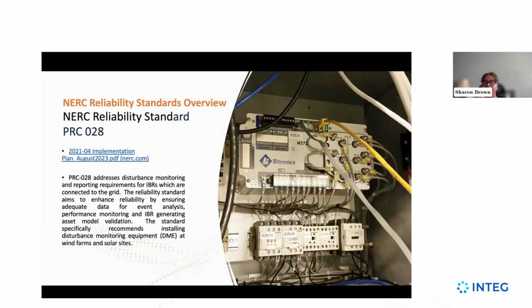You can't carry it like synchronous generation, like a big frame unit with all that metal spinning, the inertia. You can't ride through a fault like a gas turbine carries frequency. But because of the amount of penetration in certain markets, particularly like ERCOT, it's literally no longer an option for folks to just drop off and say, okay, we had a fault, we're disconnecting from the grid. That's the way it used to be, right? Well, here, that dog don't hunt anymore, as my grandmother used to say. And FERC has seen, with the various disturbances, that the implications are vast for grid reliability if that happens.